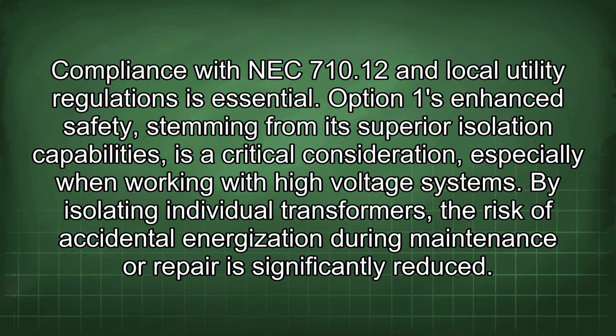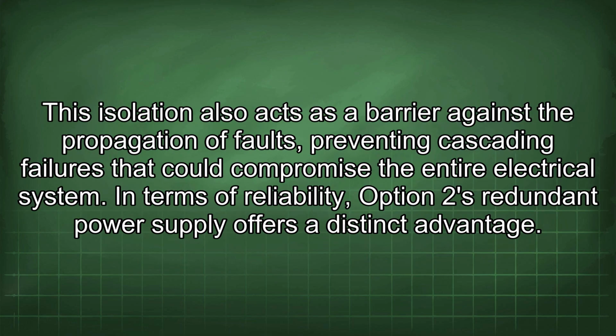Option 1's enhanced safety, stemming from its superior isolation capabilities, is a critical consideration, especially when working with high-voltage systems. By isolating individual transformers, the risk of accidental energization during maintenance or repair is significantly reduced. This isolation also acts as a barrier against the propagation of faults, preventing cascading failures that could compromise the entire electrical system.